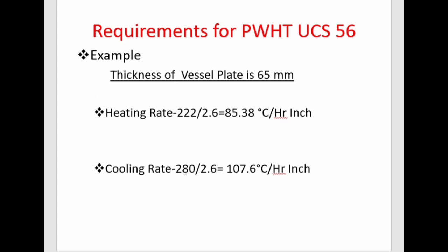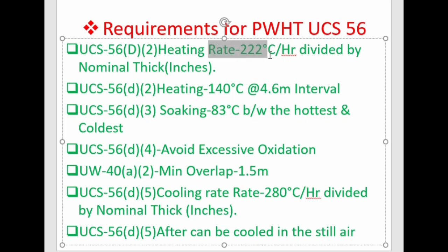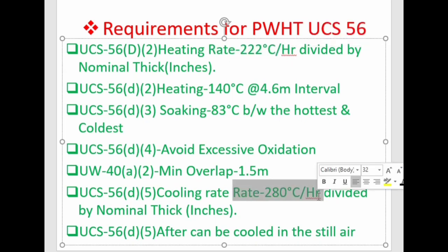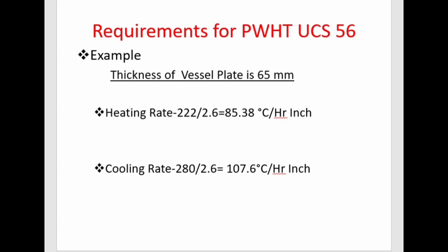Here is a sample example to find the heating rate and cooling rate. For a vessel with a plate thickness of 65 mm, which is equivalent to 2.6 inches: the heating rate shall be 222 ÷ 2.6 = 85.38°C per hour, and the cooling rate shall be 280 ÷ 2.6 = 107.6°C per hour, using the formulas from UCS-56 D2 and D5.